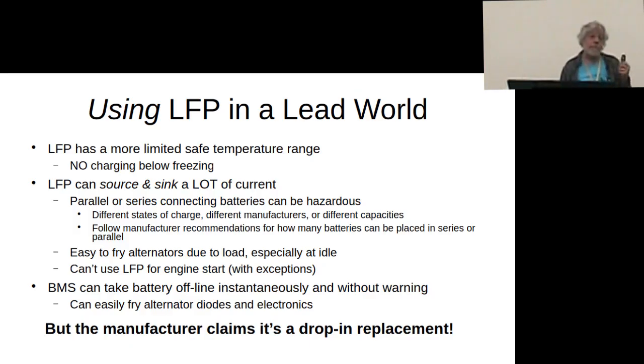You can connect lead acid batteries, regular flashlight batteries, in series and parallel, and people do that all the time. But read the instructions on your lithium iron battery - some of them you can't connect in series. If you want 48 volts, you don't necessarily put 4 of them in series; it depends on the brand. Some of them have limits on how many you can put in parallel, usually 4. Some you can do 16. Can you do 30? Probably not.